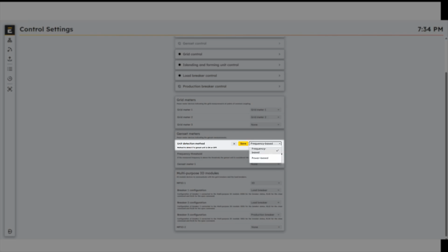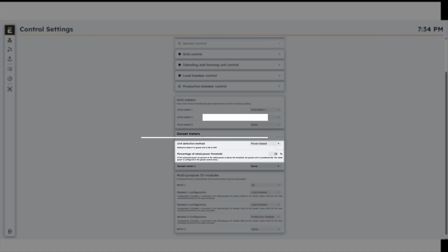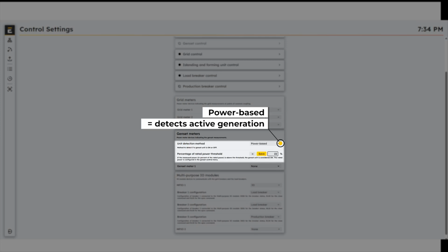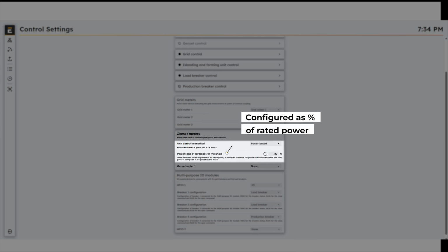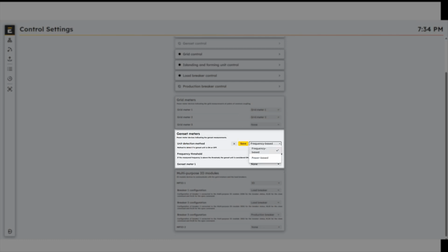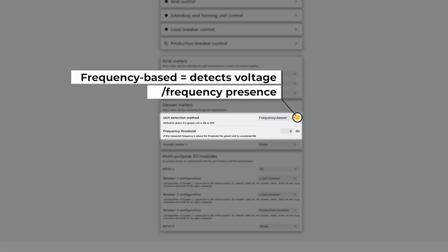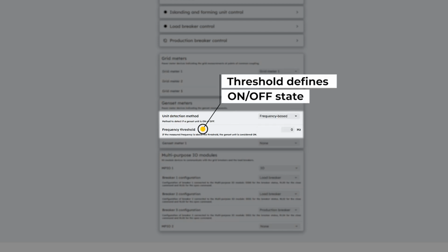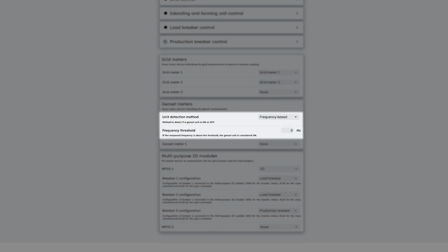In power-based mode, the system considers a Genset active when its output power exceeds a set percentage of its rated capacity, for example, 22%. In frequency-based mode, the generator is considered running when the measured frequency rises above the configured threshold. These parameters ensure accurate state detection across different generator types and scenarios.